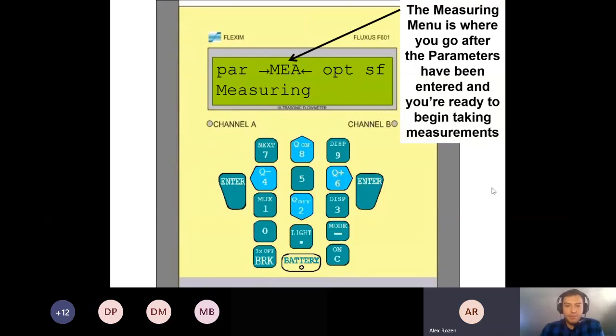So we use the portable flow meter a lot at wastewater and water treatment plants. And a lot of times we're not sure whether the pipes are lined or not. So I wanted to ask if there's any kind of good assumption to be made most of the time. I think typically we just assume it's not lined, but if there's any way to be more accurate about that assumption. It's a good assumption saying that it's not lined.